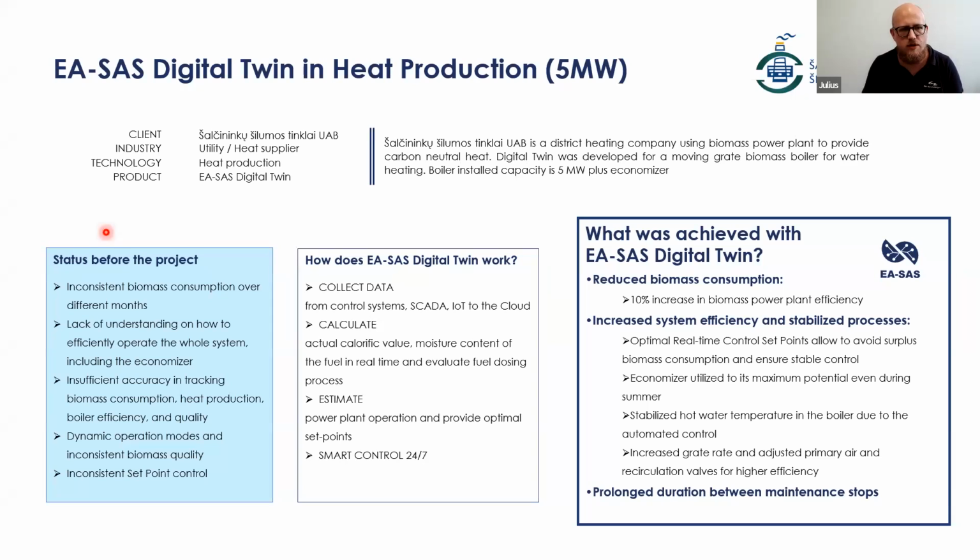Also, in this case, it's worthy to notice, I mentioned that the digital twin in the long term is an enhancer of the power plant. In their case, by using the digital twin, it was possible to see that the PLCs were seesawing. So they were coming up rapidly and then dropping, from the automation part, and you could see this over different kinds of measurement values, and you could predict when they would start to drop actually.